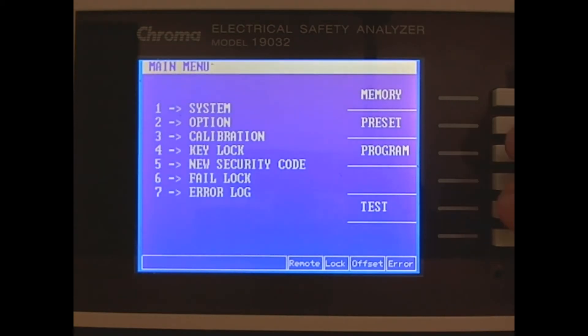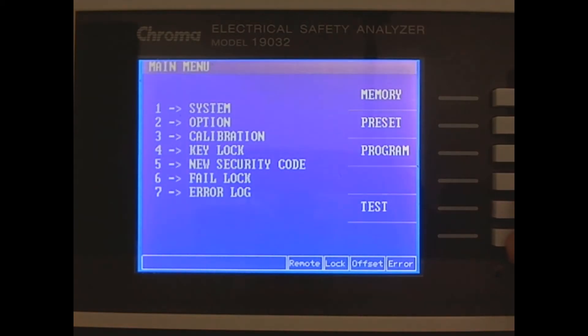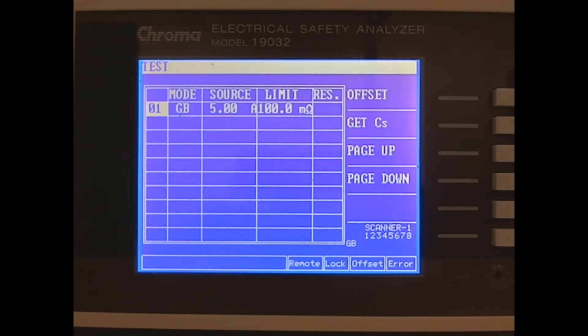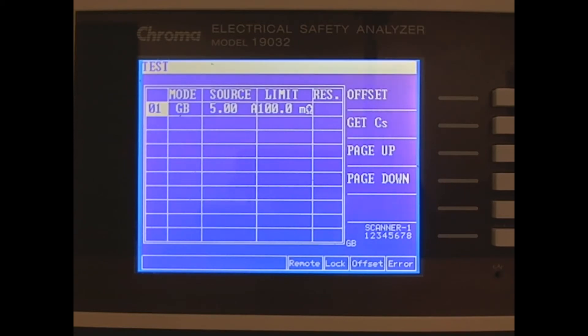Now we'll go to the main menu and choose the test button to go to the test screen. The test screen will show some of the parameters for the test we're performing. We're only doing one test. It's going to be a ground bond test. We're providing 5 amps, and we're looking for less than 100 milliohms.